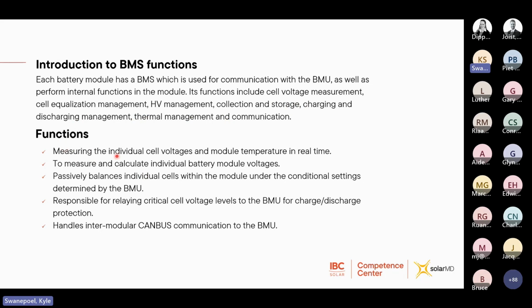So the BMS measures the individual cells. Winston, I covered that earlier. It's 114 kilowatt hours at 80 kilowatt. It measures each individual cell, as well as the temperature in real time. So each cell pack has a temperature sensor, and then the BMS also has a temperature sensor on it. So there's 3 temperature sensors on each battery module. And then it is used to calculate the individual battery voltages.